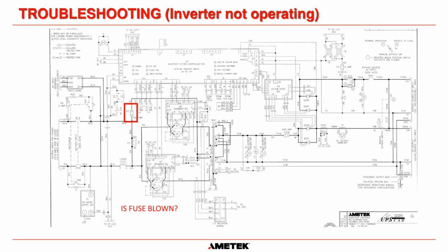And the last, I think this is the last thing we talk about on the micro-ferros, is the fuse blown. We do have F2 fuse into the bridge. Now remember, I did say earlier on, an IGBT cannot be protected by a fuse. What the fuse is there for is if an IGBT does fail, and usually fails catastrophically, then the fuse will blow after the IGBT fails to prevent any circulating high current going in, damaging the transformer or damaging any part of the system.